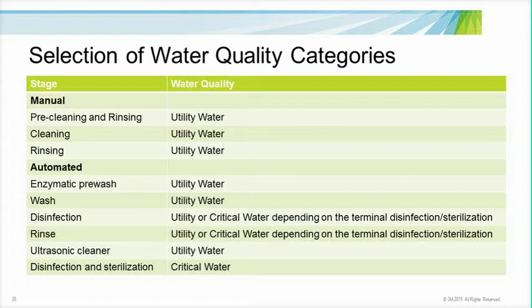And this is definitely the best practice, to ensure that that final rinse is always of a higher quality than just a utility water. It may not need to be the full critical water capacity, but it definitely needs to be more than just a utility water. This chart goes through this information in a more condensed version than in the TR34, which is covered in section 5.2, which is a lot of verbiage, so I just condensed it onto one chart to make it easier for everybody to read.